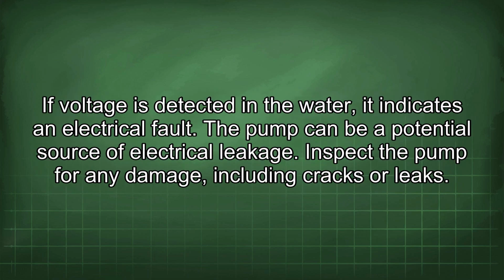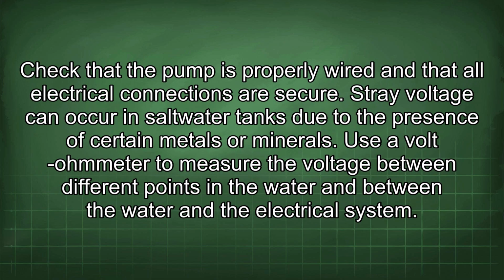If voltage is detected in the water, it indicates an electrical fault. The pump can be a potential source of electrical leakage. Inspect the pump for any damage, including cracks or leaks. Check that the pump is properly wired and that all electrical connections are secure.